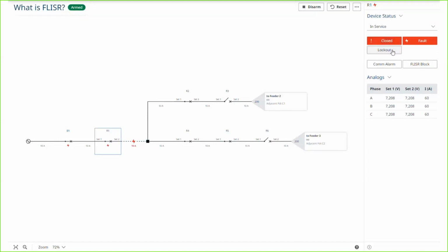As soon as the recloser locks out, FLISR should detect an event. It should know there's a fault on the line. There's a lockout accompanied by a fault indication from recloser 1. So now its job is the first 2 letters of its acronym, fault location. Locate that fault, isolate it, which you're seeing now, and restore, which you just saw. So that is the difference.